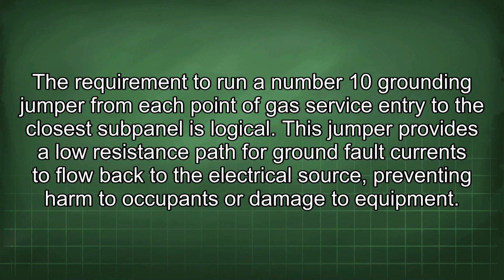The requirement to run a number 10 grounding jumper from each point of gas service entry to the closest subpanel is logical. This jumper provides a low resistance path for ground fault currents to flow back to the electrical source, preventing harm to occupants or damage to equipment.